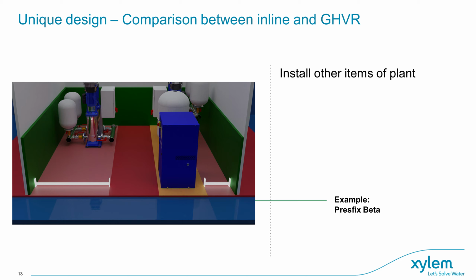With the majority of all booster sets being used for water supply to service high-rise blocks of flats, you may only get a small basement to install a booster set in. So plant room space is at an absolute premium, especially if there wasn't a booster set already fitted in that building. As water companies reduce the pressure on the incoming mains feed, and modern appliances such as showers need higher and higher pressure, booster sets are needed more and more for older buildings.